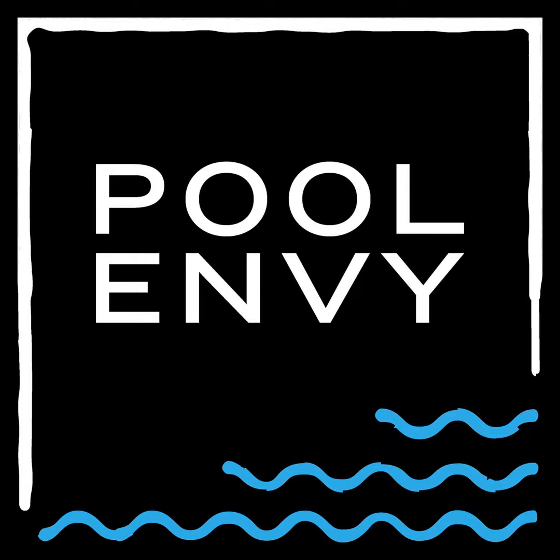And when it's not, you get the classic tingle on the pool ladder. That's not a little static. That's a voltage difference. And now your body is the bridge, perhaps over troubled water. When a pool isn't bonded, it becomes a cluster of floating electrical islands: utility neutral drifts, a transformer leak, even irrigation nearby. Each one can take a component and float it to a different potential. The moment you grab a metal rail, that difference equalizes through you. People die from it, though. Not from a short circuit, from a few volts that never had a safe path to equalize. Equipotential bonding eliminates that path. Every conductive point shares the same potential. No difference, no current, no shock. Simple, elegant, invisible.